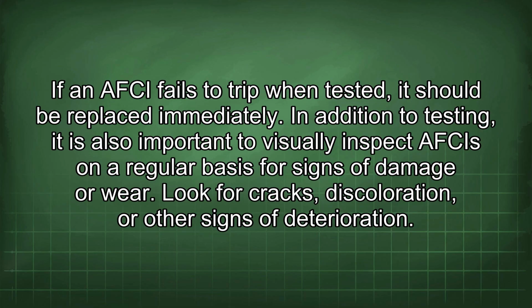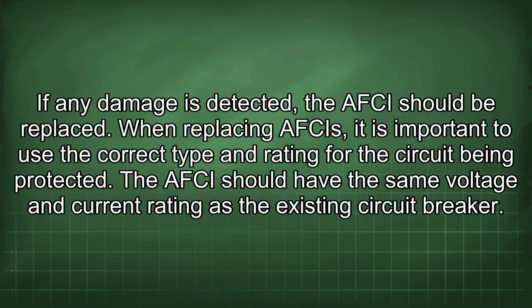Look for cracks, discoloration, or other signs of deterioration. If any damage is detected, the AFCI should be replaced. When replacing AFCIs, it is important to use the correct type and rating for the circuit being protected. The AFCI should have the same voltage and current rating as the existing circuit breaker.